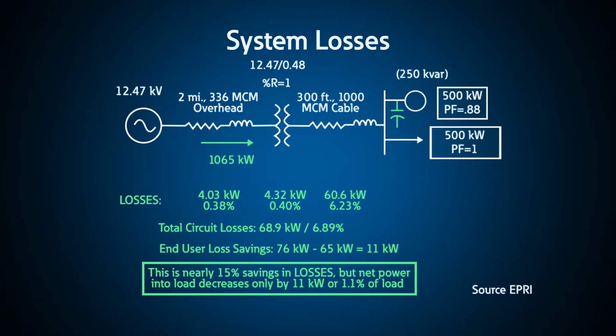For a total system loss of 76 kilowatts, you can save 11 kilowatts by installing capacitors, saving 15% of the losses, but in reality only 1.1% of the power bill. Installing them closer to the utility would result in negligible energy savings from I²R losses. Note, however, that to avoid a power factor penalty, they can be anywhere downstream of the utility meter.